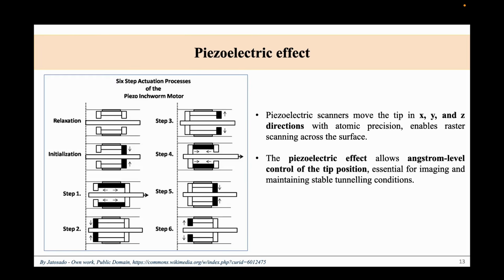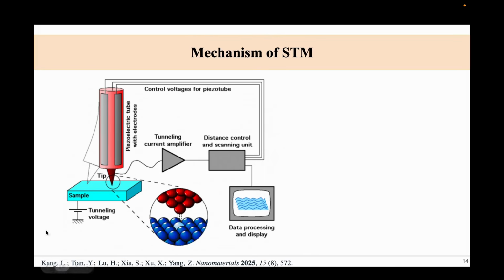So without piezoelectric control, STM would not be able to maintain stable tunneling conditions or generate accurate atomic scale images. Now that we have looked into everything, let us see how the mechanism of STM works. In this figure, the sharp tip is attached to the piezoelectric tube with the electrodes and the sample is placed just below it.